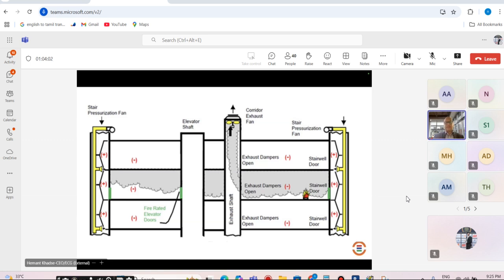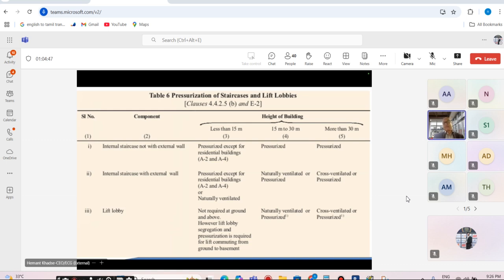So importantly, when an engineer like you is responsible for designing the systems, make sure that it is also documented well in the form of as-built layouts or in the manual, handed over to the operation team with the training, with the AMC plan, so that the system is effectively used in a real emergency case. Maybe in the next 10 years it need not be used at any point in time in a fire emergency, that's fine. But if at all it is required, how does it need to respond? So the engineer's responsibility is not only to design, but also to document it.